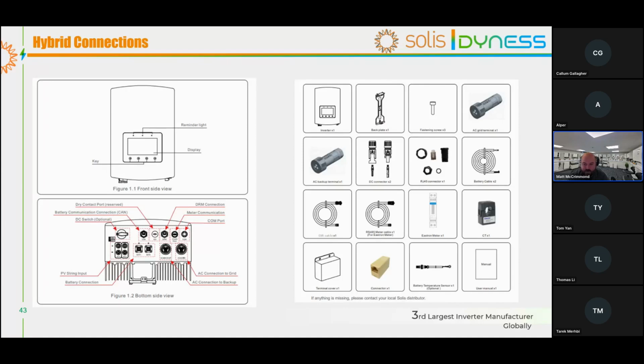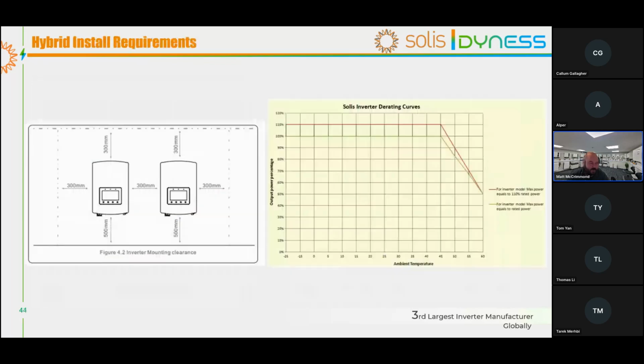We then have the meter plus the CT. There are some important facts that we'll talk about in a short while, in terms of meter positioning and the CT cable. And then we also have the manual, of course. That's ultimately what you get in the box. So everything is as plug and play as it can possibly be from a Solis perspective. You should be able to do the install based on what you have. We also have suggested tools in our manuals, so you can consult the manuals through our website before you even approach site, so you're fully equipped with all the information you require.